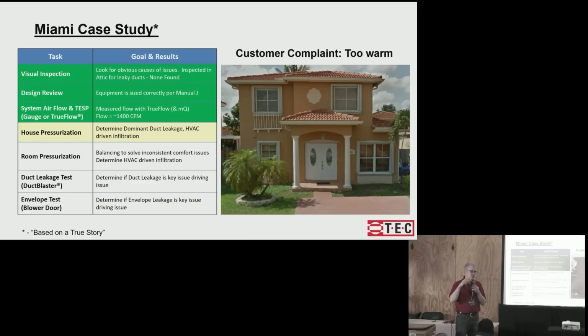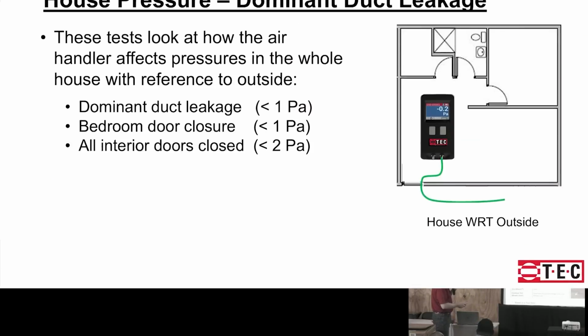If the HVAC system is taking all of its air from inside and returning it back to inside, then turning the HVAC system on should not change the pressure in the house. If it changes the pressure in the house, then that means that air is either leaving the duct system to outside or it's getting sucked in from outside, depending on whether you go positive or negative. So let me explain what that test is.